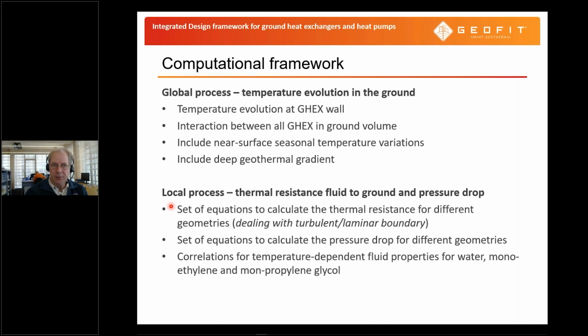In the computational framework, like I indicated before, we have to deal with the global process, which is the temperature evolution in the ground. Then we have the temperature at the ground heat exchanger wall, but also the interaction between all the different ground heat exchangers in the specific ground volume. Furthermore, because we're talking about shallow heat exchangers, we need to include the near surface seasonal temperature variations. In summer, the shallow earth will be warmer. In winter, it will be cooler. And if the whole heat exchanger is at shallow depth, these variations need to be considered.